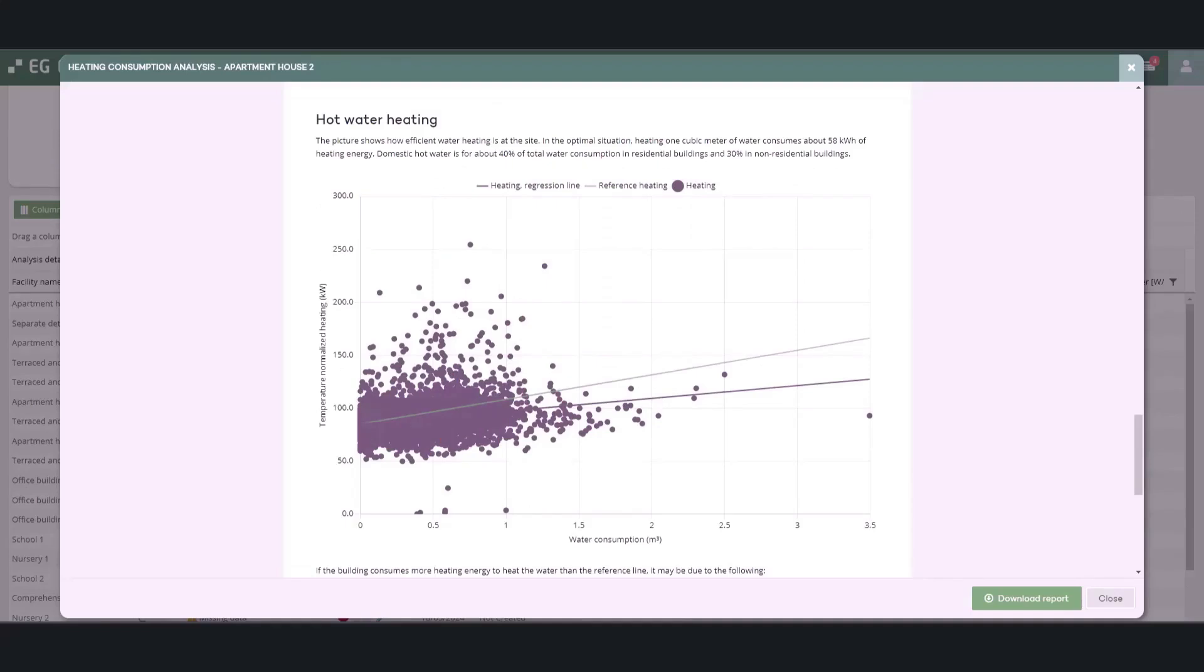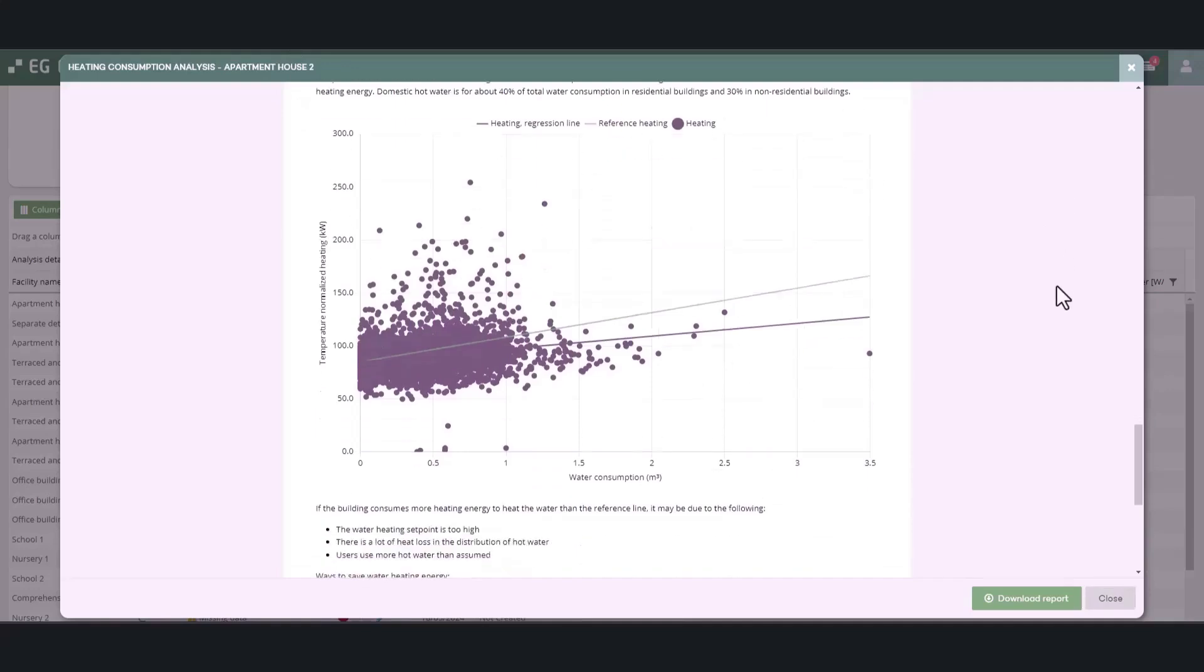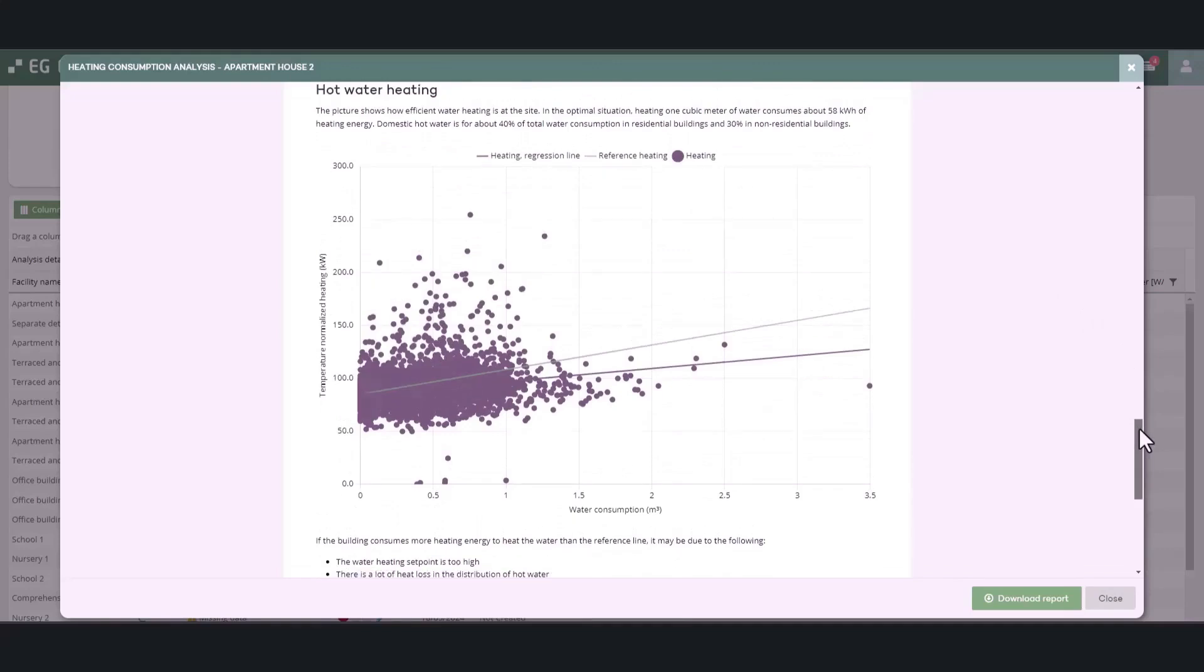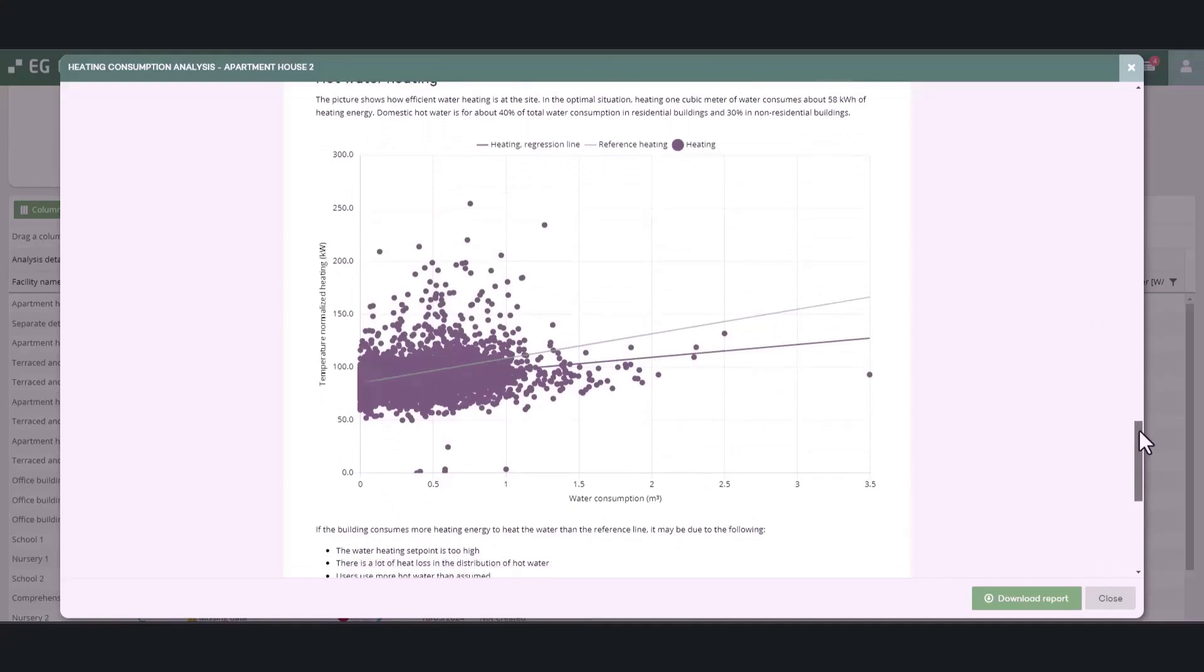In facilities where ventilation is on at a constant power, it is possible to determine the energy efficiency of domestic hot water heating. In a normal scenario, about 58 kilowatt hours of energy is used to heat one cubic meter of water.